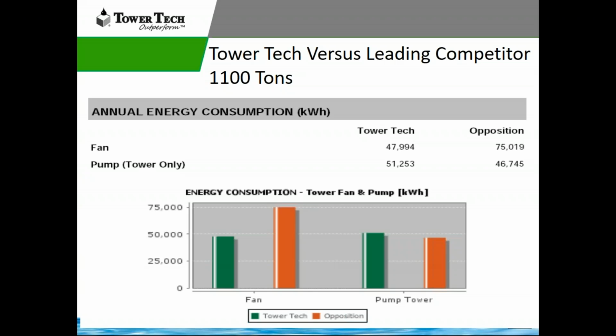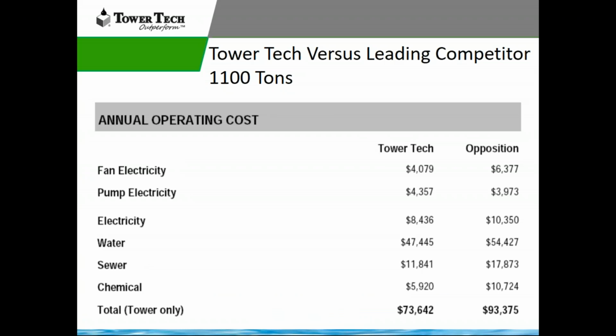And then from a fan system, we were saving some on the fan, but you'll notice I'm not playing favorites here. In this case, it took a little more to pump the water through our machine, so we had to take a 5,000 kilowatt hour hit on the pump side of this tower. However, when we look at the overall savings of the job, it was about $20,000 a year in operating cost savings between fan, electrical, water, sewer, and chemical.